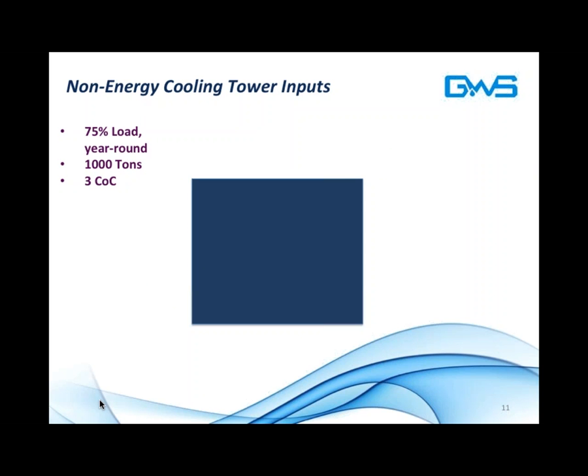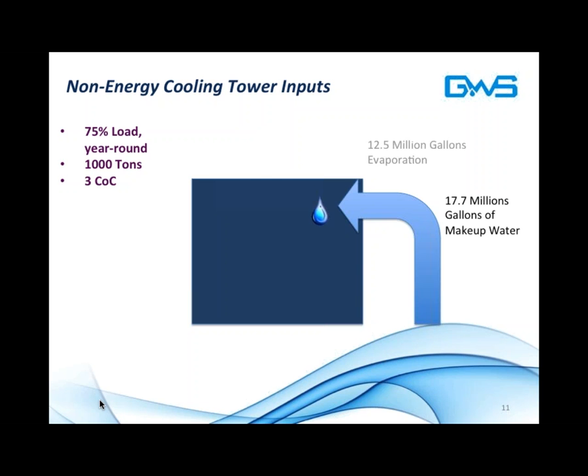Consider the non-energy cooling tower inputs. We're going to leave energy aside, even though that's a significant chunk of costs associated with a tower. For an example tower, this square represents a cooling tower operating at 75% load year-round, akin perhaps to a data center. 1,000 tons of cooling at 3 cycles of concentration. A tower of this size will consume almost 18 million gallons of makeup water per year. That's a lot. That's approximately 26 Olympic-sized swimming pools every single year. Because evaporation is constant, 12.5 million gallons approximately will be evaporated into the atmosphere, roughly 70% of the total makeup.